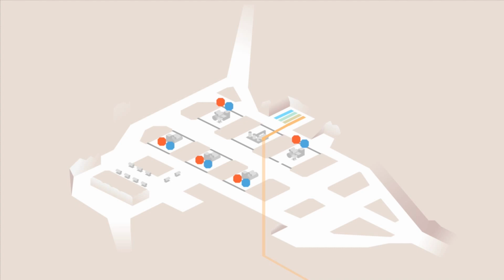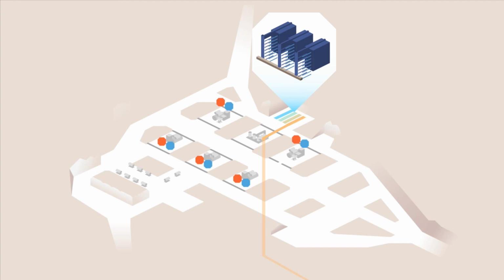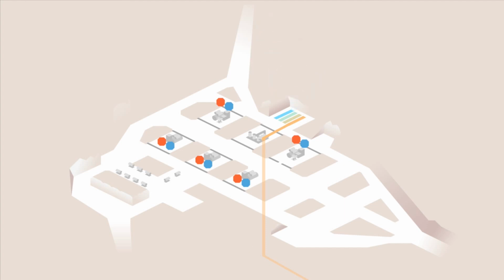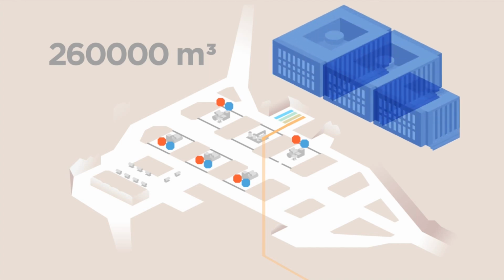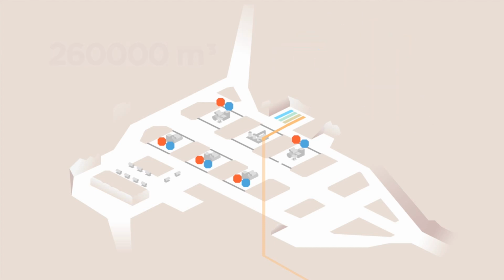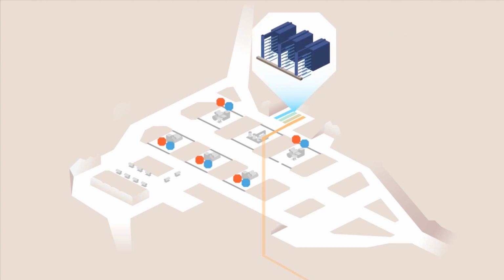At Katrivala, the water is directed through filters into the sewage water heat exchangers. Depending on the time of year, the water comes to the plant at a temperature of 10 to 20 degrees, and its flow rate is about 260,000 cubic meters per 24 hours. This corresponds to the volume of 2.5 parliament houses. The heat of the purified sewage water is utilized in the sewage water heat exchangers. Cooled sewage water is directed to the open sea through the discharge tunnel, and the recovered heat goes to the heat pumps.